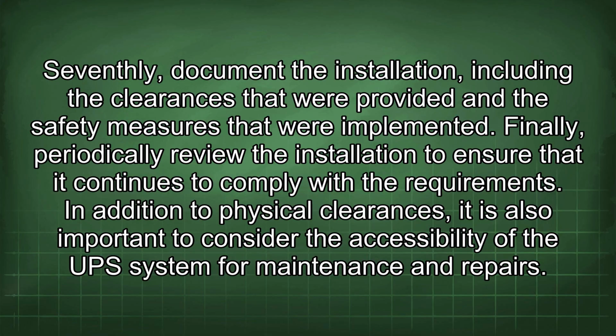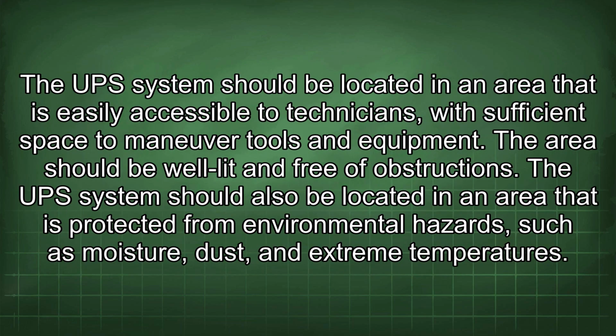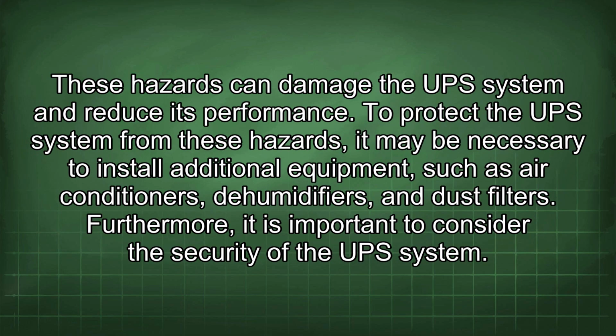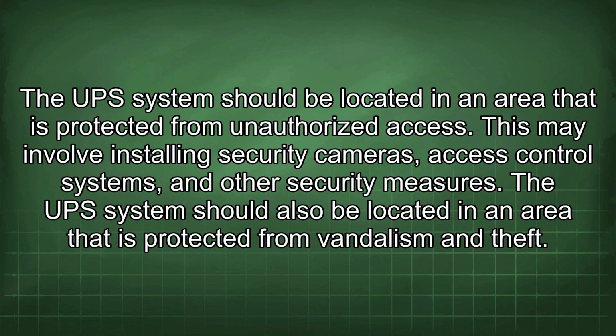In addition to physical clearances, it is also important to consider the accessibility of the UPS system for maintenance and repairs. The UPS system should be located in an area that is easily accessible to technicians with sufficient space to maneuver tools and equipment. The area should be well lit and free of obstructions. The UPS system should also be located in an area that is protected from environmental hazards such as moisture, dust, and extreme temperatures. These hazards can damage the UPS system and reduce its performance. To protect the UPS system from these hazards, it may be necessary to install additional equipment such as air conditioners, dehumidifiers, and dust filters. Furthermore, it is important to consider the security of the UPS system. The UPS system should be located in an area that is protected from unauthorized access.